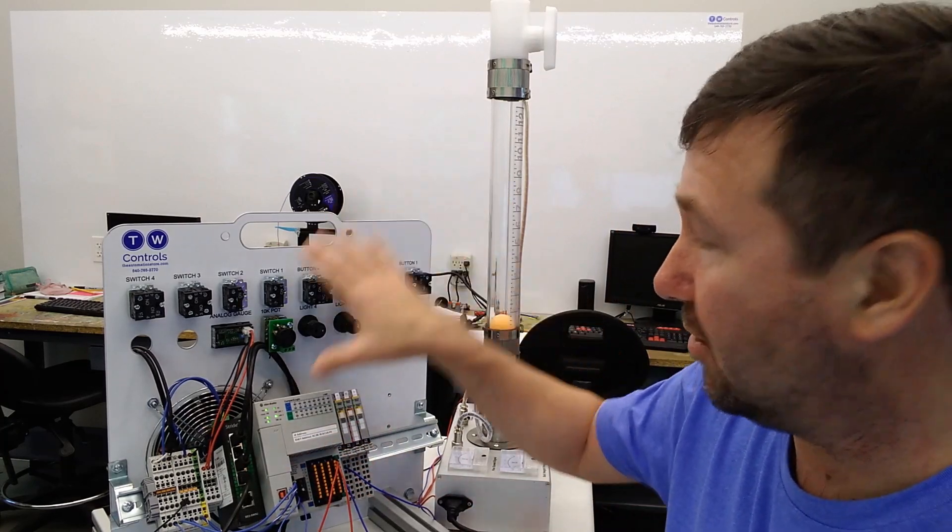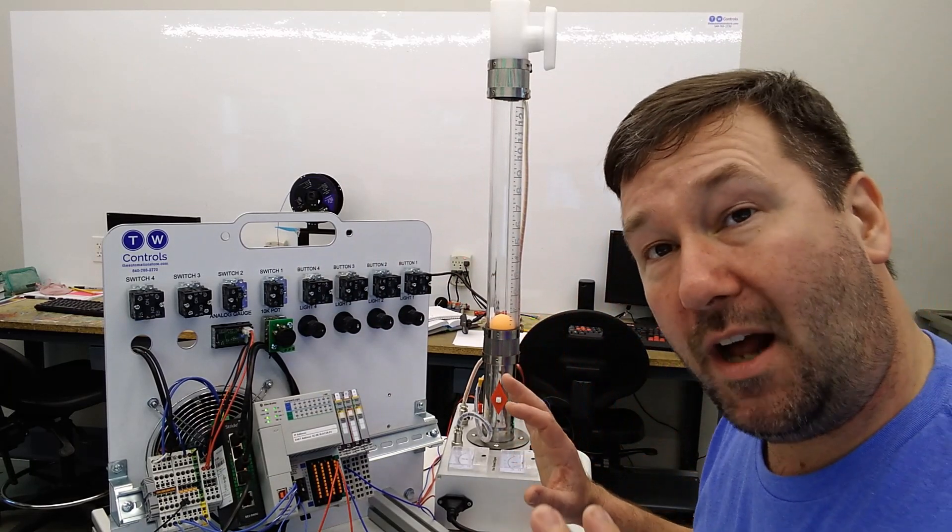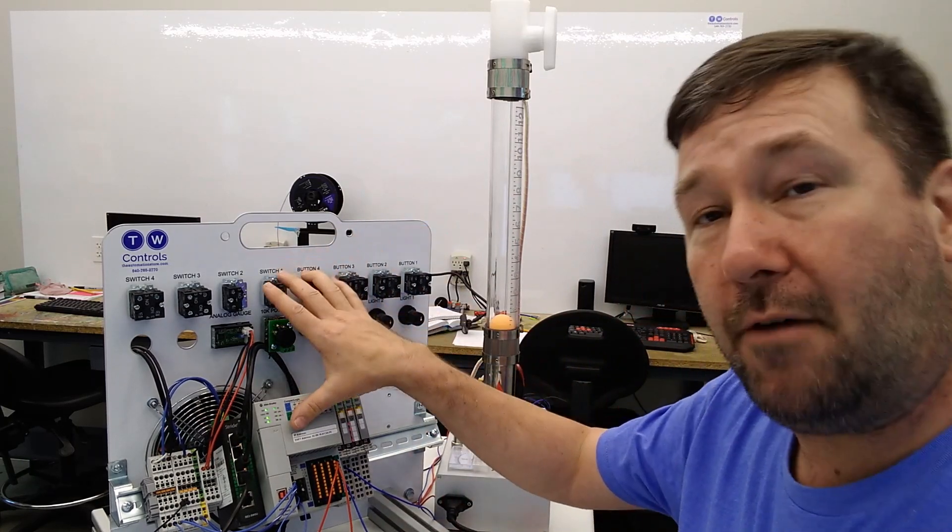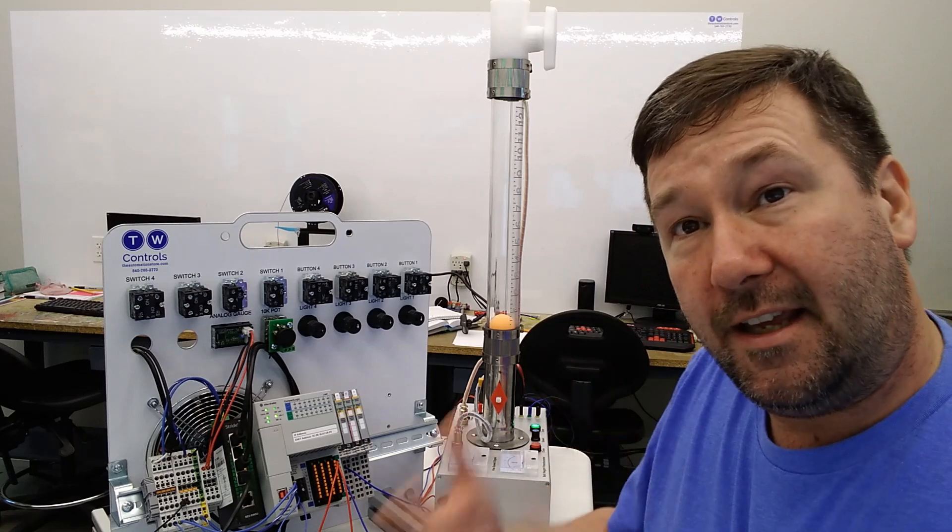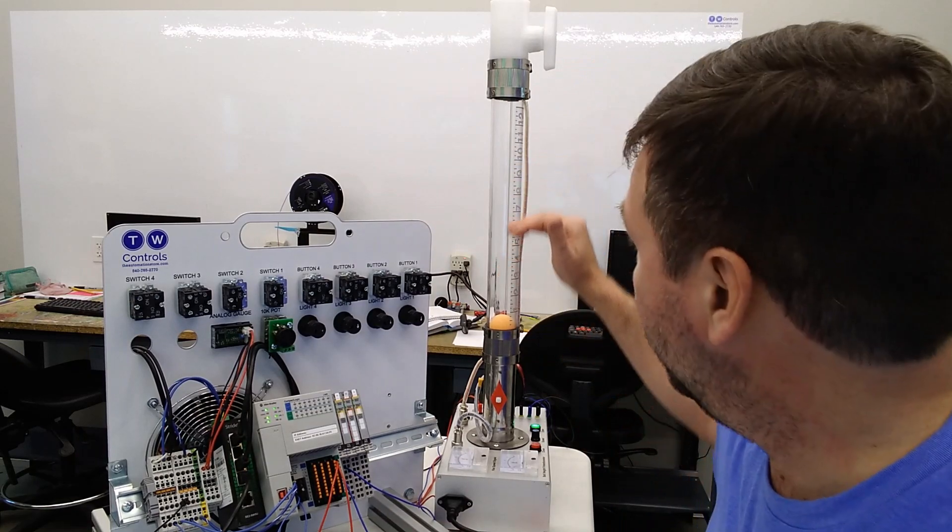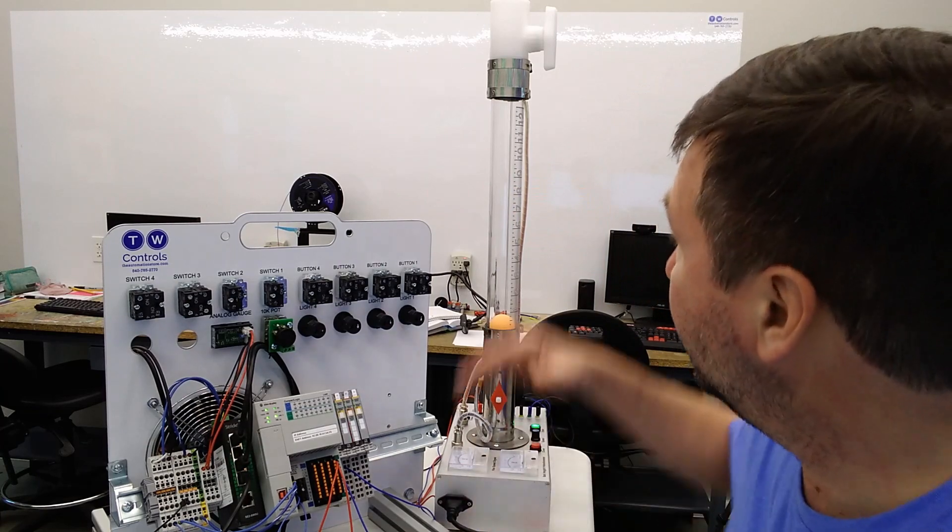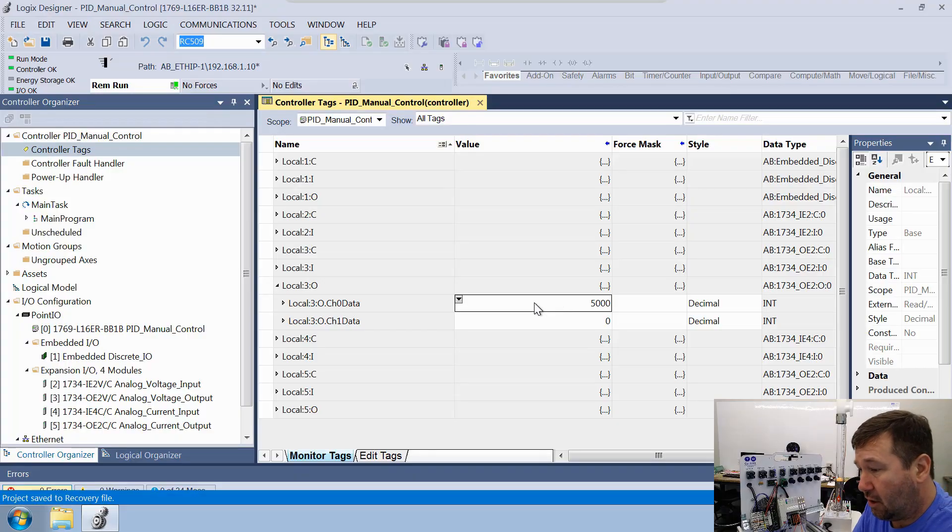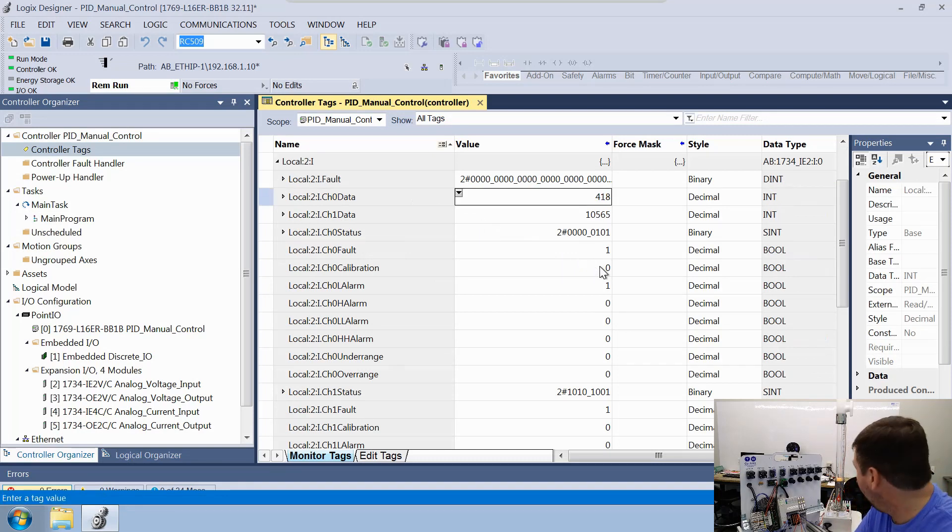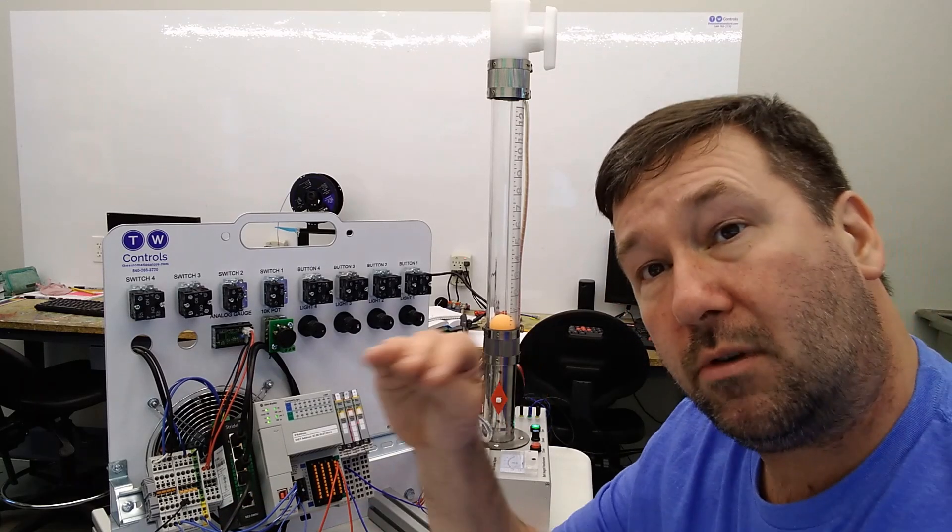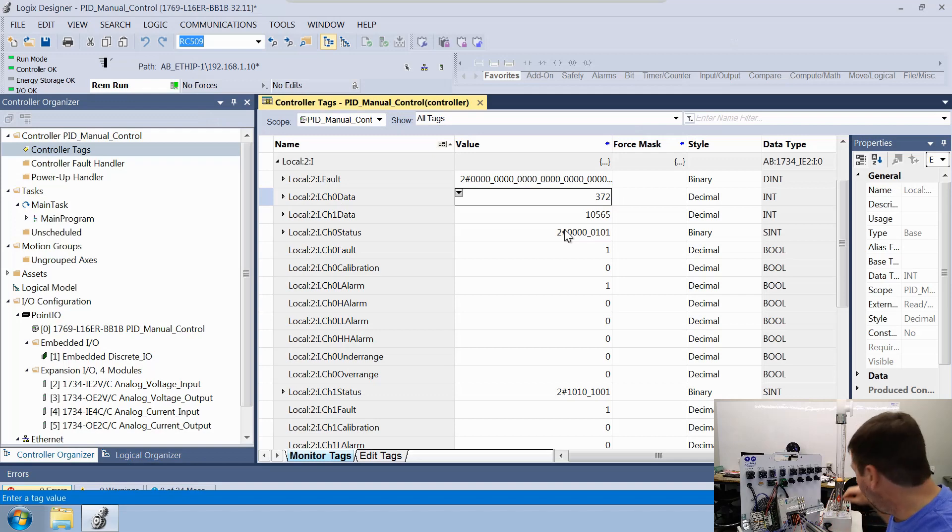For this video, we are using our CompactLogix trainer, and we're using Industrial Concepts PID trainer. If you're coming into this series and you haven't watched our beginning videos, I'll put a link to those in the description, because we go through how we interfaced our PLC trainer with the PID trainer, and also we've done an overview of it. In our last video, we created our basic program, and we used our analog output to manually position the ball where we want it. In this video, the first thing we need to do is actually look at this level sensor and get it scaled so that we can read it in some units. Our level sensor is connected to Module 2, so we're going to go into local:2:I, and then right here, channel 0 has it. It's sitting at the bottom right now, and let's call that 400. Our low level is going to be 400 units on our analog range.